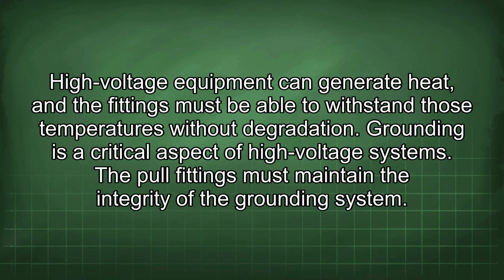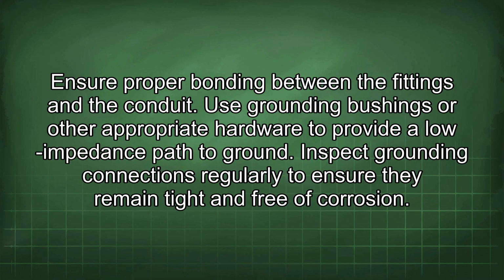Grounding is a critical aspect of high-voltage systems. The pull fittings must maintain the integrity of the grounding system. Ensure proper bonding between the fittings and the conduit. Use grounding bushings or other appropriate hardware to provide a low-impedance path to ground. Inspect grounding connections regularly to ensure they remain tight and free of corrosion.